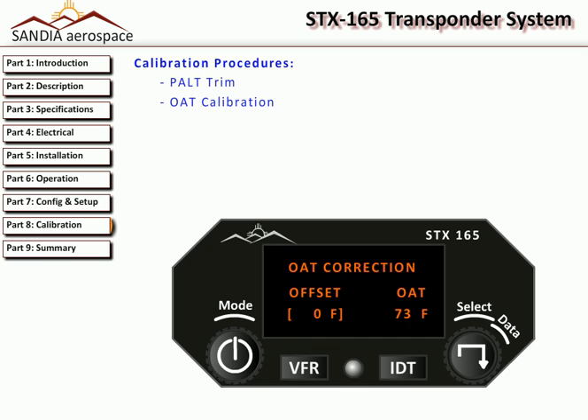Before beginning this procedure, you will need to obtain a known, stable temperature for the OAT probe. It is recommended that you place a calibrated temperature sensor next to the OAT probe to find the current ambient temperature. On the STX-165, you will find a temperature readout on the OAT correction page. Press the Enter button to edit this value.